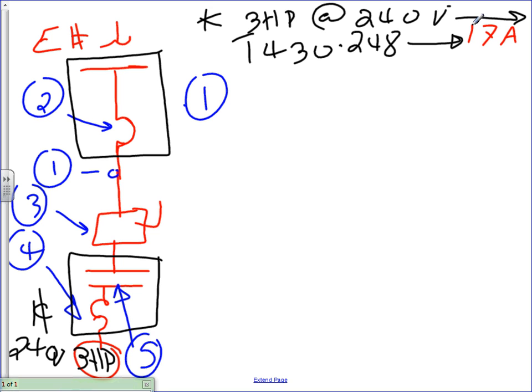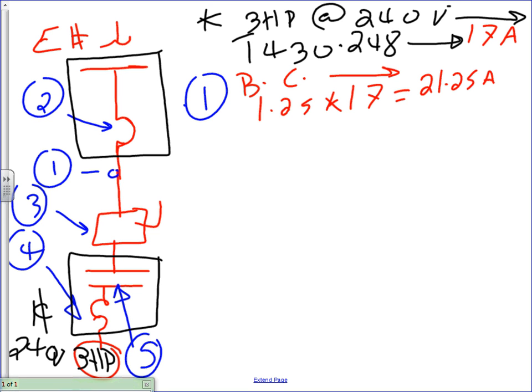So when we find conductors, guys, we'll do this one, conductors, motor, branch circuits. Okay, so we're going to go, it's continuous load. So when we find, number 1 is branch circuit. How do you size a branch circuit? You take 1.25, you multiply it by 17, and I need somebody to do a calculator for me fast. 17 times 1.25. 21.25 amps. Cool. Okay, so it's continuous load. Based on the NEC code book, it's going to be continuous load. All right, so continuous load branch circuits. Good to go.